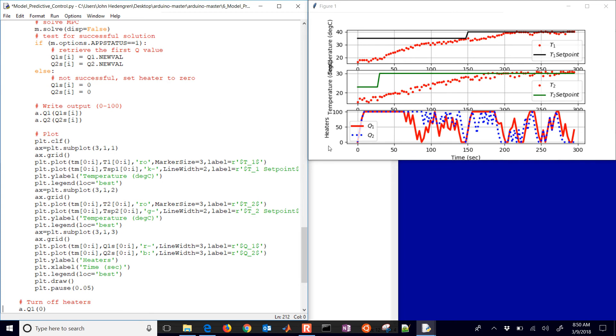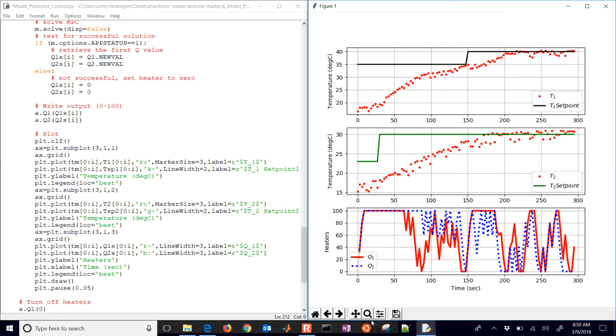Our model predictive controller ran for five minutes and was able to reach the setpoints. You can adjust the tuning to make it faster or slower, more or less aggressive. One thing to consider is that Q1 and Q2 show a lot of fluctuation. For certain systems — like where there's a valve or pump — you don't necessarily want to open and close it rapidly in succession. Think about MV or CV tuning to reduce manipulated variable fluctuation when needed.